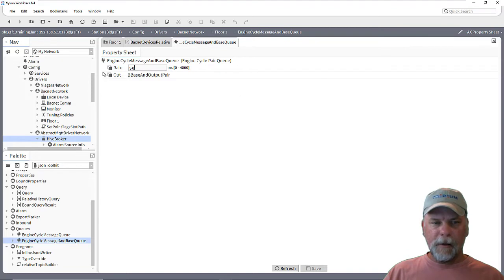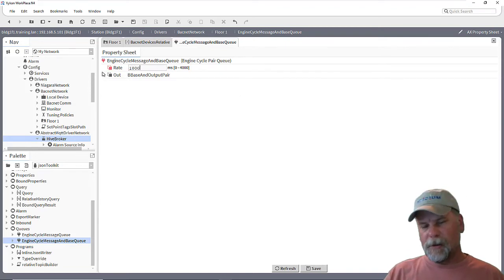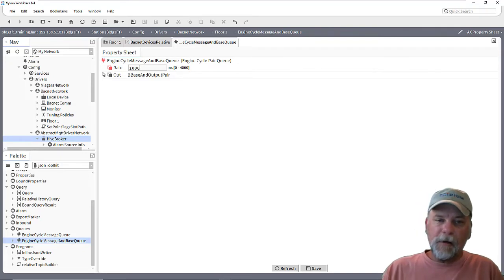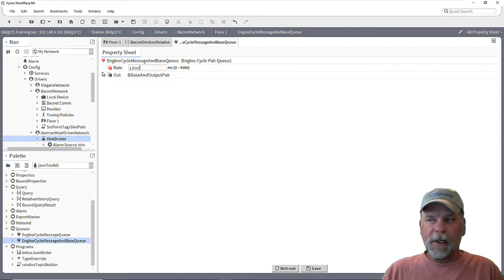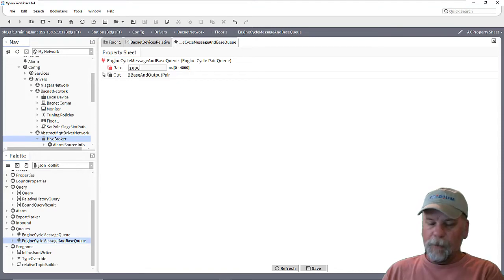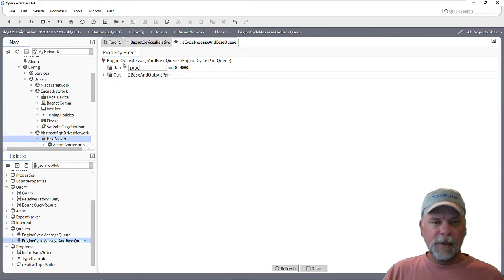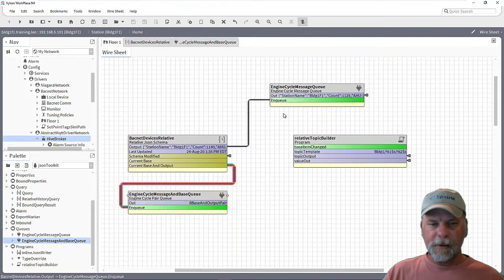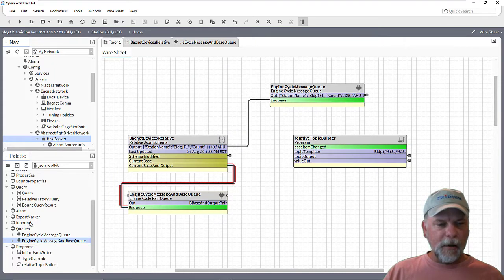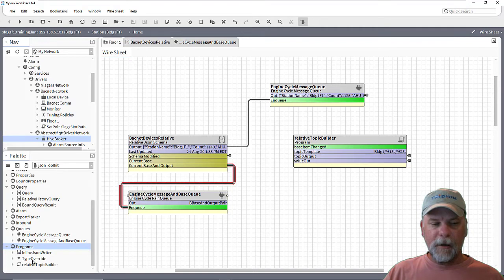And then just to slow things down a little bit so that we can see, particularly in the wire sheet, what's going on. I'll go in here and clear the hidden flag on the rate component or the rate slot on that queue component rather. And then I'll set this to something like one second. Now that's probably much slower than it needs to be. You might need to tweak it from the 50 milliseconds on a Jace, a PC probably not. In this case, I'm really trying to slow it down so that we can see what's going on here basically.